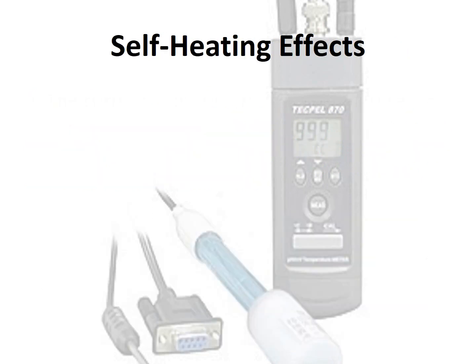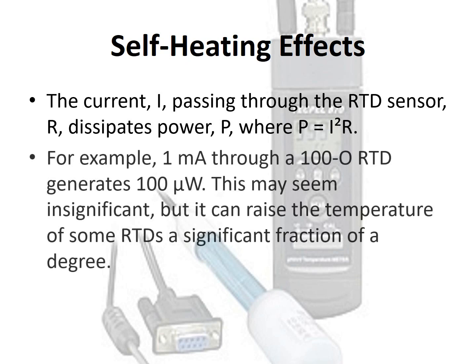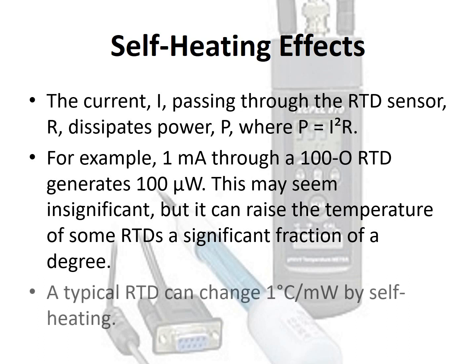Regarding self-heating effects: the current I passing through the RTD sensor R dissipates power P, where P = I²R. For example, 1 milliampere through a 100 ohm RTD generates 100 microwatts. This may seem insignificant, but it can raise the temperature of some RTDs by a significant fraction of a degree. A typical RTD can change 1°C per milliwatt due to self-heating.